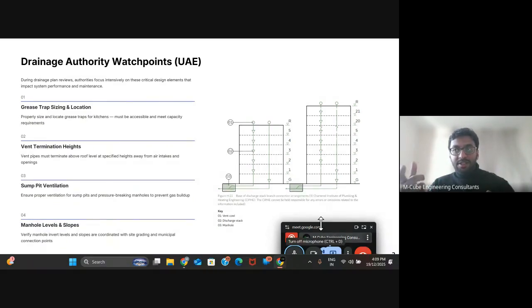Generally, the easiest way is to just take a branch from the manhole, take the vent pipe and put it onto the compound wall, but it does not meet the design intent. Again for sump pits, what we see in buildings is ventilation being missed, and pressure pipe is not shown, and pressure breaking manholes are missing.